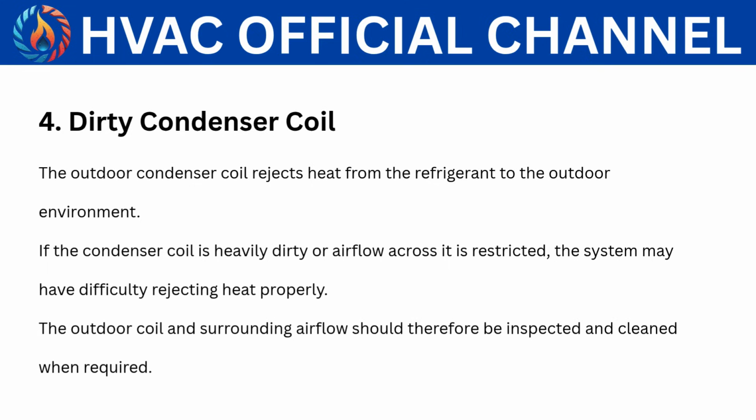4. Dirty condenser coil. The outdoor condenser coil rejects heat from the refrigerant to the outdoor environment. If the condenser coil is heavily dirty or airflow across it is restricted, the system may have difficulty rejecting heat properly. The outdoor coil and surrounding airflow should therefore be inspected and cleaned when required.